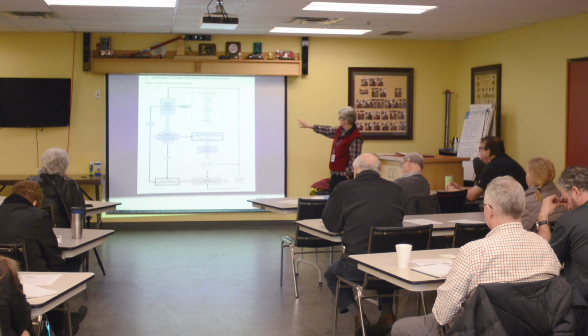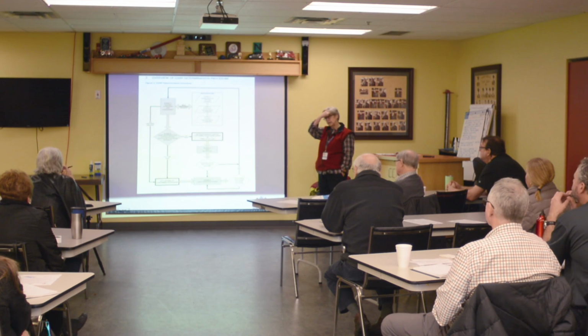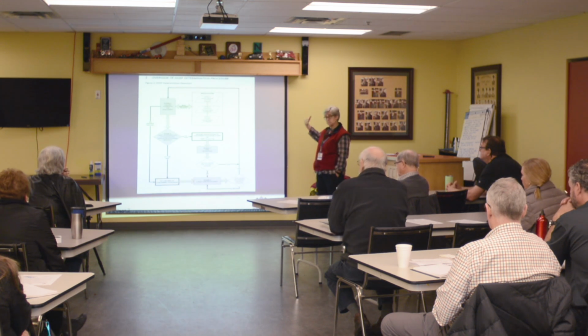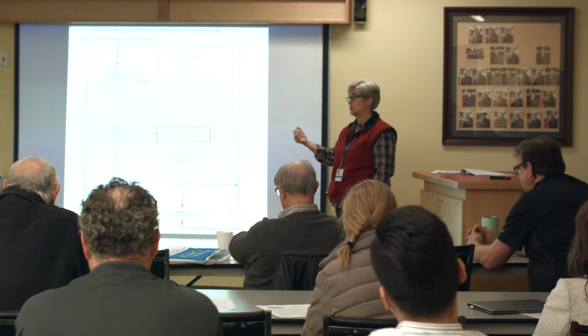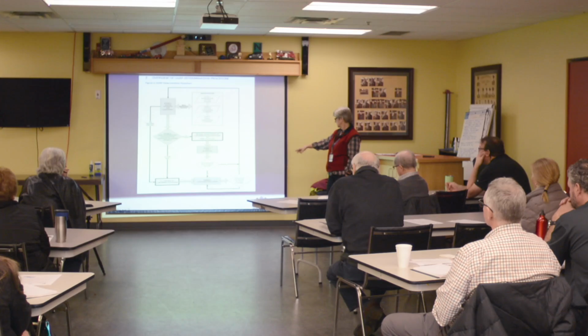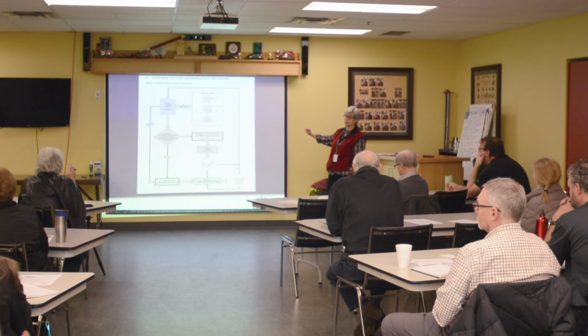Once you've looked at whether or not it is GARP, the stage 1 hazard screening and assessment is a checklist. If you have certain things on there, it may be at risk of containing pathogens, and therefore you may want to look a little more. If there's no hazard present, you'll come down to the very bottom, at low risk of containing pathogens. You might go to long-term monitoring, but it would always be an ongoing thing that you'd always be looking at. If something changes, you may want to look at it again and see if those changes are impacting your water.